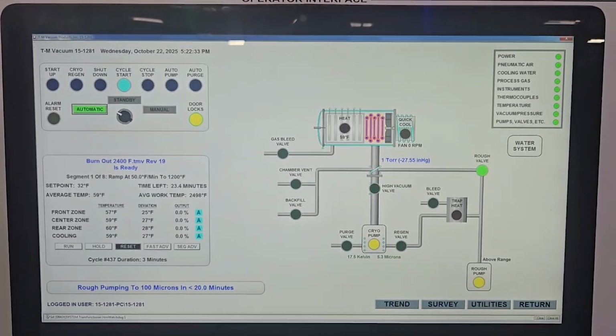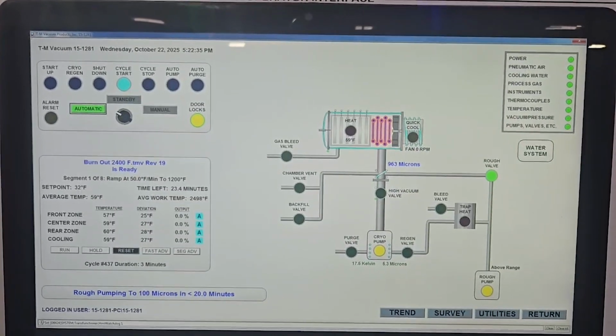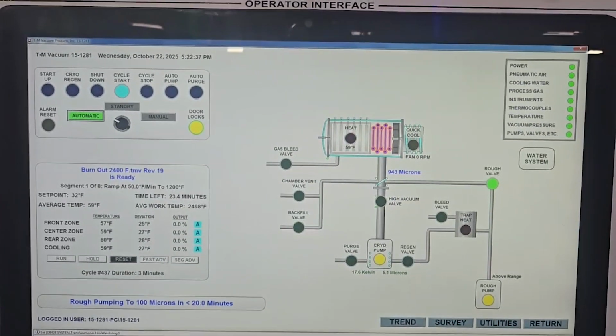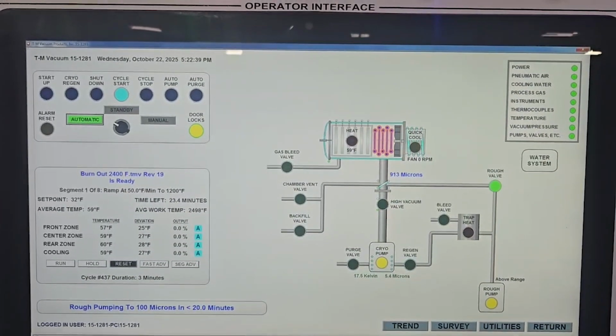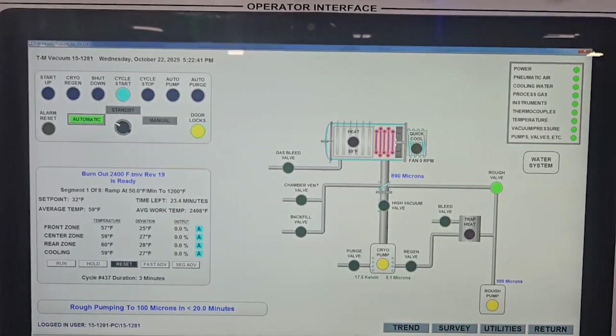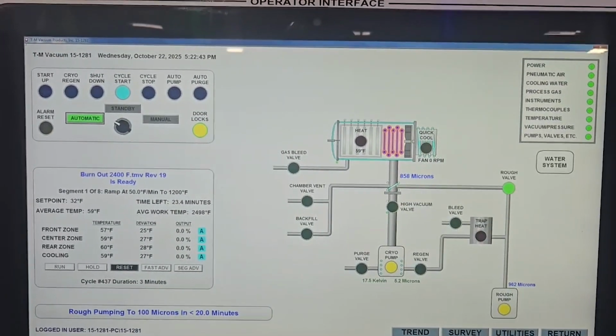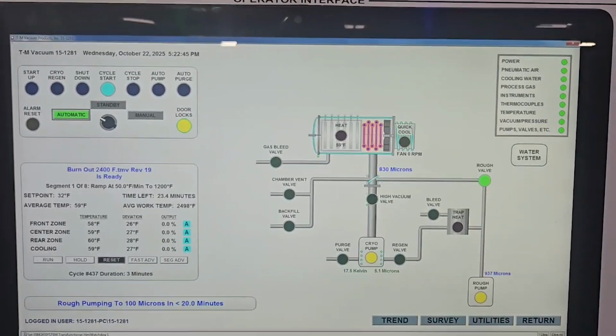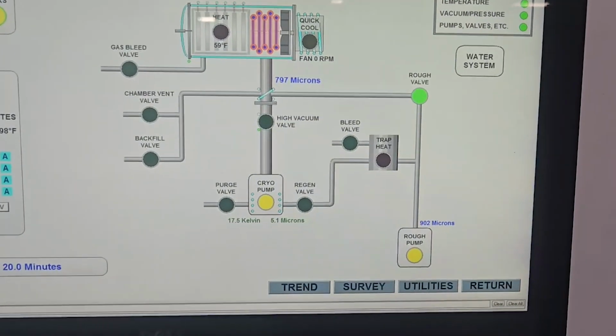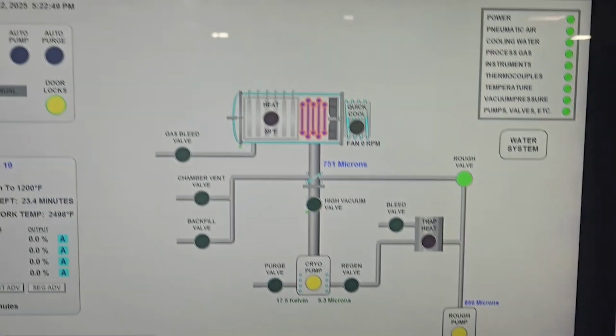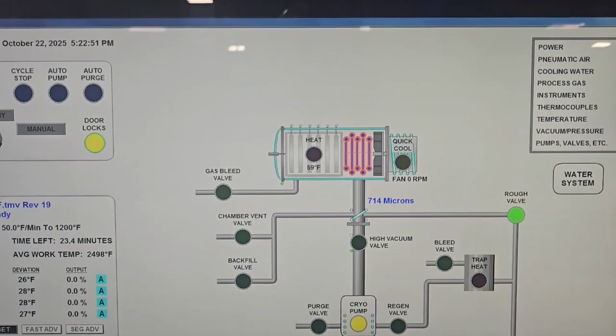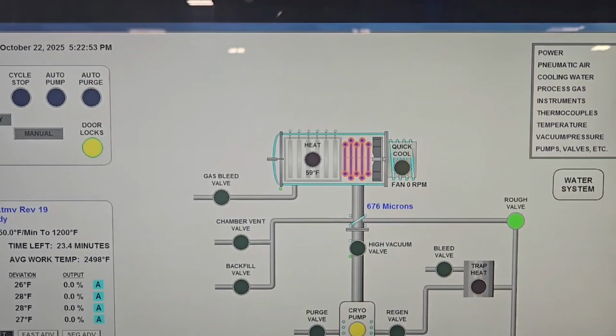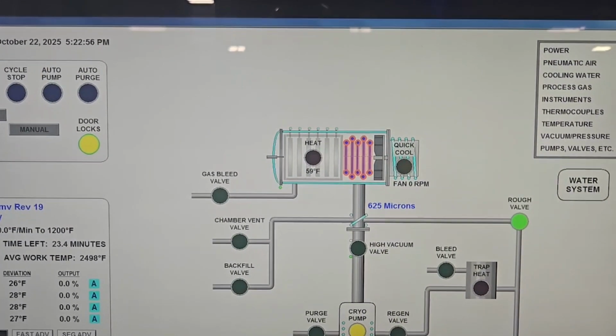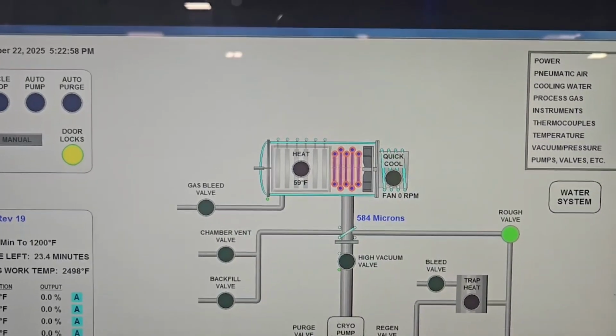I've just started the unit. The cryo pump is down to 17.5 Kelvin. I've started a burnout cycle, which is what you will run weekly or intermittently to keep your chamber clean. You can see the rough pump has come on. It's bringing the torr down. Right now it's just past 1 torr, and it's dipping down into microns right now.